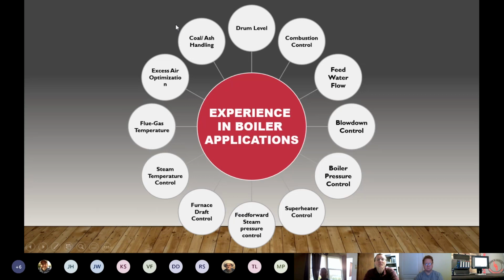In some of the larger utilities, the old way of doing things was to have a UDC 6000 or a Foxboro or a Taylor Instrument, and have several of those in a panel, each controlling one of those loops, hardwired, feeding information back to each other so that you could do things like master boiler control and feed forward and things of that nature. In the HC900, you don't have to worry about all that. You can combine all of those control loops into one I/O rack and wire everything into that one I/O rack, which makes things a lot cleaner.